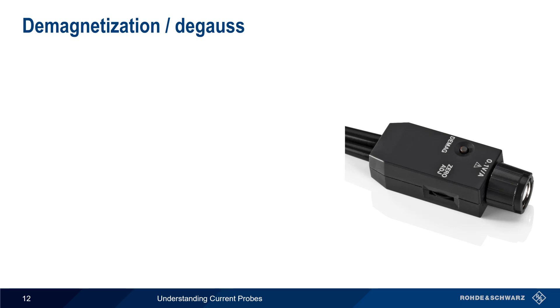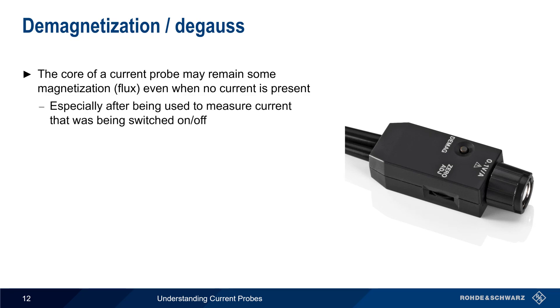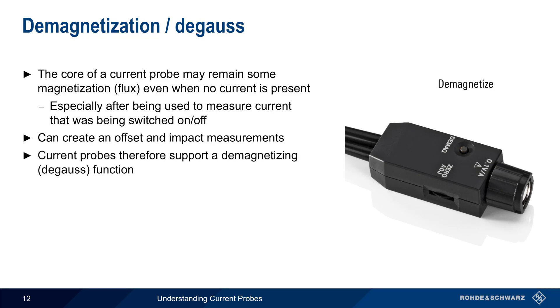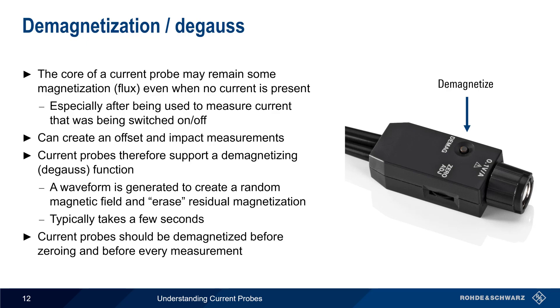Another potential issue is that the ferromagnetic core of the probe may retain some magnetism or flux, even when there's no current present. This is not uncommon after a probe has been used to measure a current that was being switched on and off. This residual magnetism can lead to an offset and impact measurement results. Current probes therefore support a degauss function that can be performed either from the probe itself or via the scope's user interface. A special waveform is generated that creates an essentially random magnetic field, erasing any residual magnetism in the probe — a very quick process that only takes a few seconds. It's a good idea to degauss the probe both before zeroing and before making any measurements.